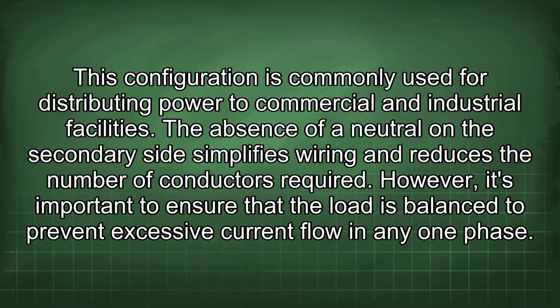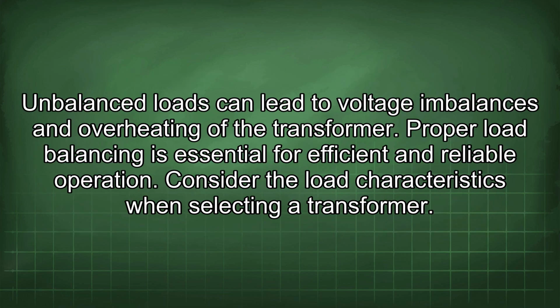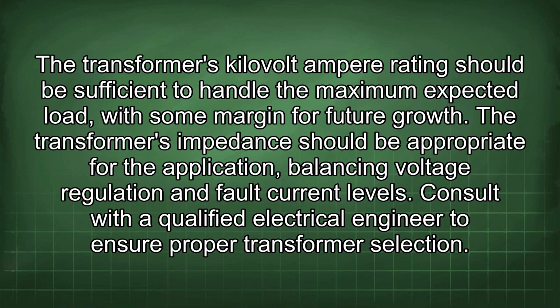However, it's important to ensure that the load is balanced to prevent excessive current flow in any one phase. Unbalanced loads can lead to voltage imbalances and overheating of the transformer. Proper load balancing is essential for efficient and reliable operation. Consider the load characteristics when selecting a transformer. The transformer's kilovolt-ampere rating should be sufficient to handle the maximum expected load, with some margin for future growth. The transformer's impedance should be appropriate for the application, balancing voltage regulation and fault current levels. Consult with a qualified electrical engineer to ensure proper transformer selection.